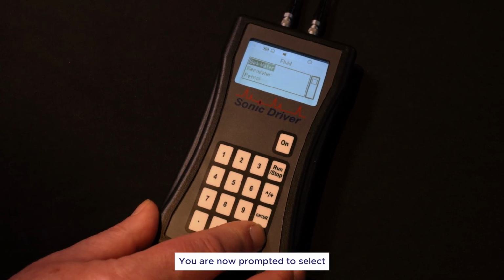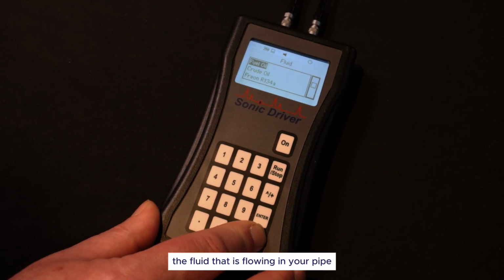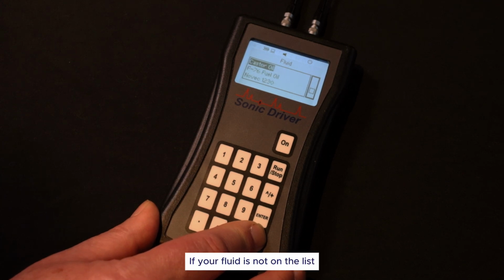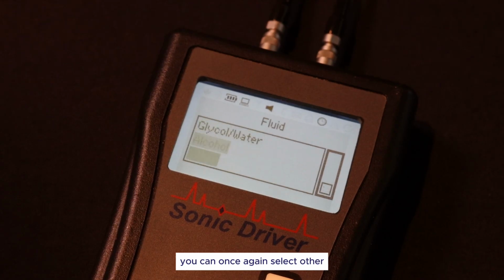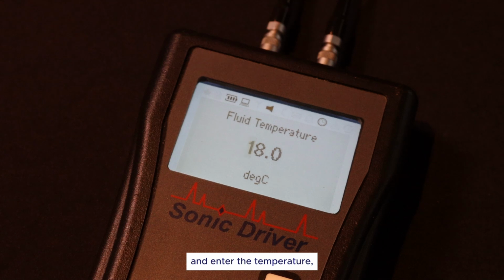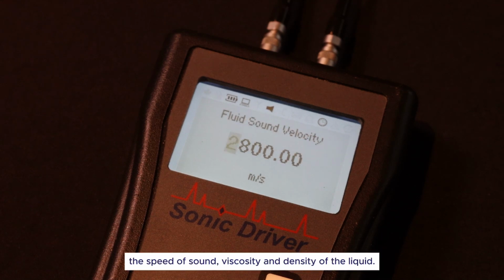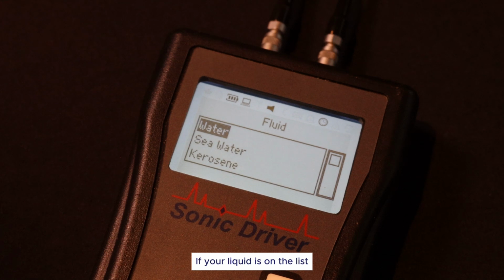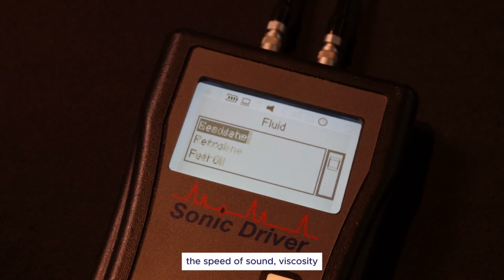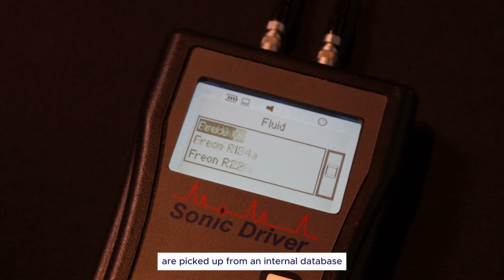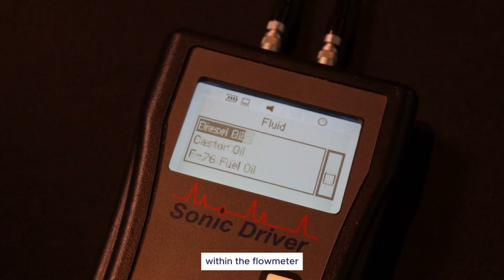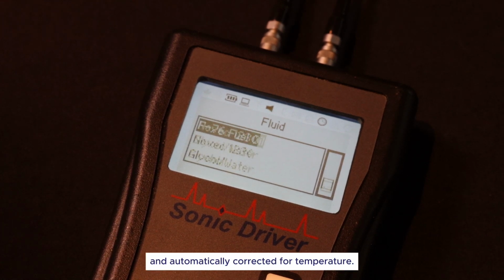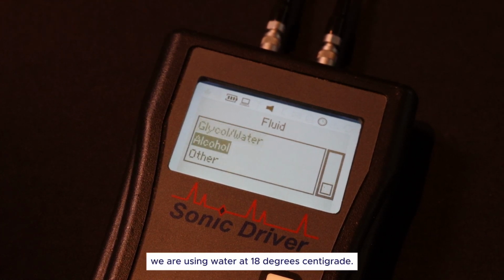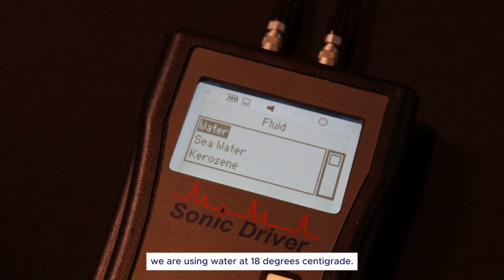You are now prompted to select the fluid that is flowing in your pipe from a list. If your fluid is not on the list, you can once again select Other and enter the temperature, the speed of sound, viscosity and density of the liquid. If your liquid is on the list, the speed of sound, viscosity and density are picked up from an internal database within the flow meter and automatically corrected for temperature. In this example, we are using water at 18 degrees centigrade.